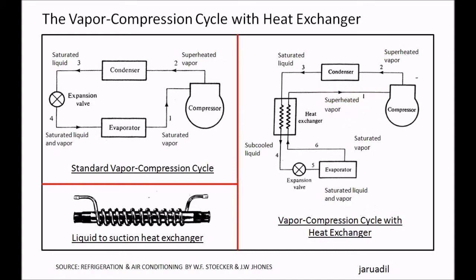That is the difference of the vapor compression cycle with heat exchanger. This is the heat exchanger — sometimes it looks like this. The tube coils around inside. Since both coils are in contact, one type of refrigerant flows inside the tube and the other is on the outside, so there is an exchange of heat between them. This is the liquid-to-suction heat exchanger.